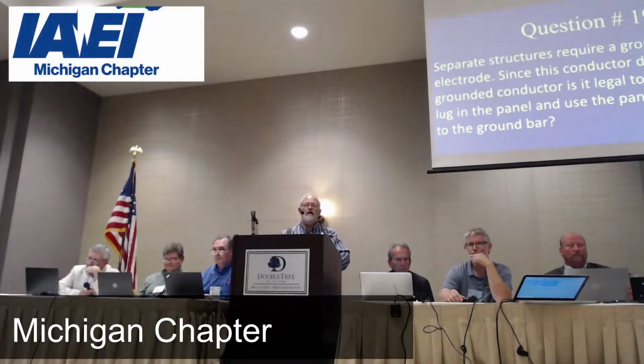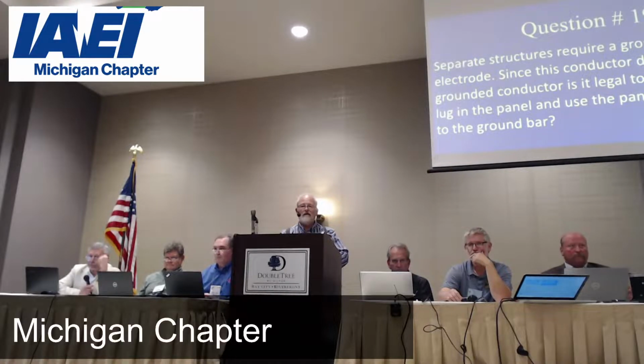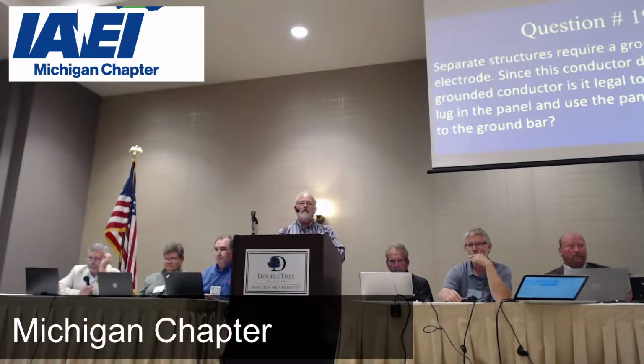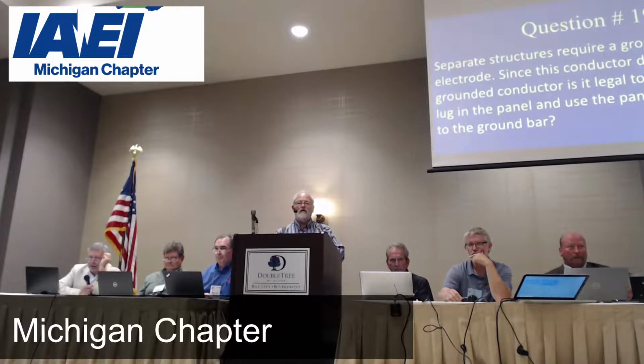No, 250.118 is equipment grounding conductors, not grounding electrode conductors. Right. Yeah, get somebody at the mic over here too. My question is if you ground or bond that to the cabinet, and you're grounded to your grounding electrode system, are you using the cabinet as a fault path? Last time I knew, UL doesn't list the cabinets to carry the fault path. Exactly. Well, under those conditions, no, you can't bond that to the cabinet, because you're using the cabinet as a path, unless there's a cabinet out there that I'm unaware of that you can use as a path.